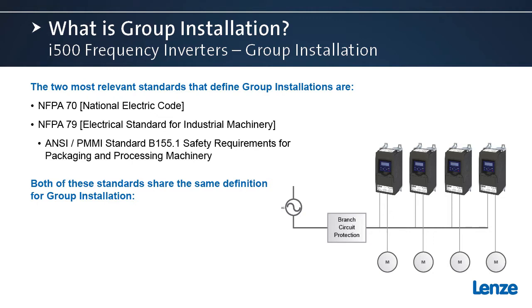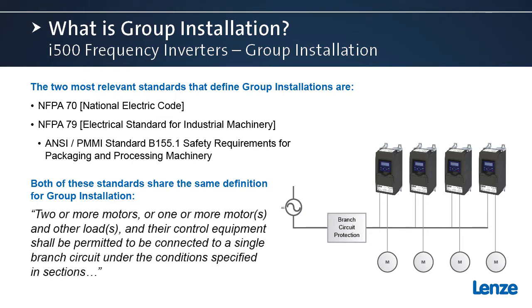What is group installation? NFPA defines group installation as two or more motors or one or more motors and other loads and their control equipment shall be permitted to be connected to a single branch circuit under the conditions specified. And what they're really saying there is you're allowed to have two or more motors and controllers, in this case frequency inverters, protected by a single branch circuit protective device. So instead of individual branch circuit protectors in front of each frequency inverter, you just have a single branch circuit protector, so you can minimize the number of components and things in the machine.